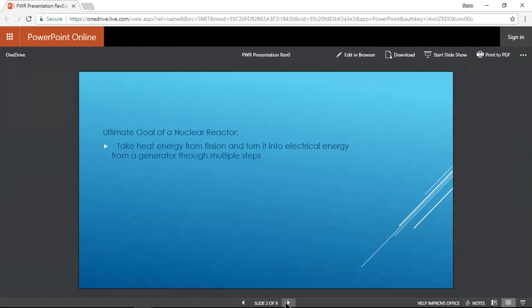One misconception I think people have is they think that most of the heat is generated from the actual fission itself. That's a common misconception. Most of the heat that's generated comes from the fission fragments that are produced. Yes, in addition to, obviously, the two or three neutrons that are produced that go on to continue the criticality. So you have these highly energetic kinetic energy fission fragments that are vibrating very, very fast, and those will then, through inelastic collisions, transfer that to the moderator, which in this case will be water. And then the water heats up. That's how we extract the heat energy.